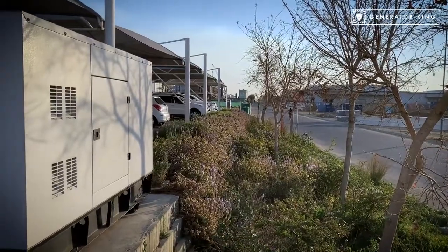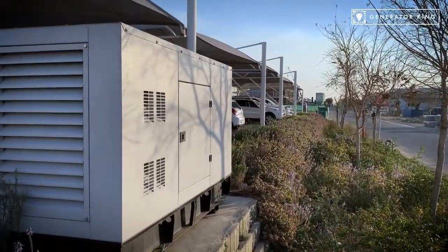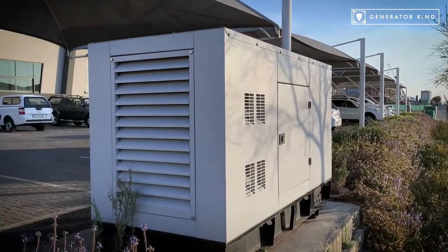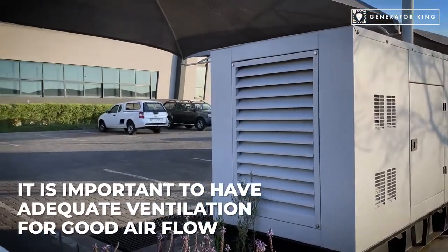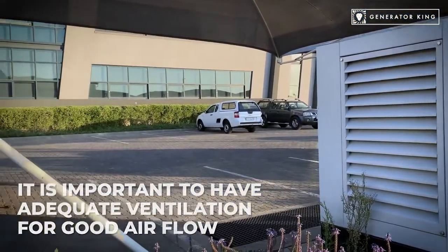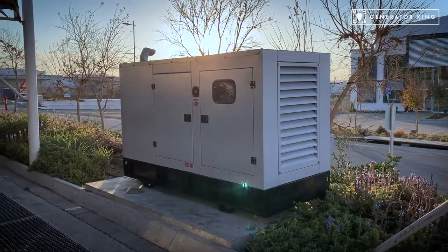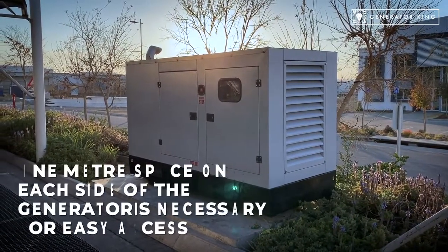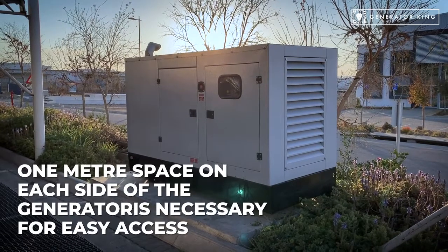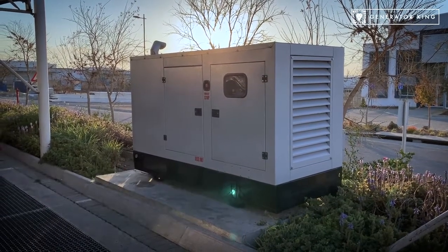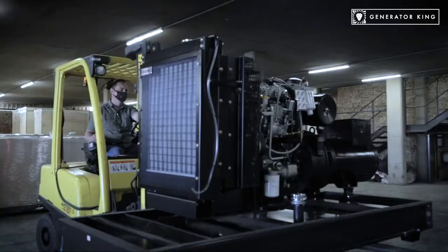The generator can be positioned inside or outside, but it is very important that there is adequate ventilation to ensure good airflow and circulation. There also needs to be sufficient space to open the doors for the servicing of the generator, approximately 1 meter on either side of the generator set.